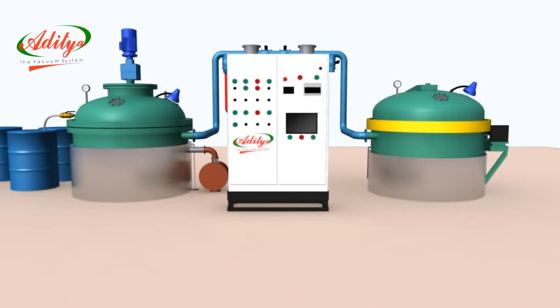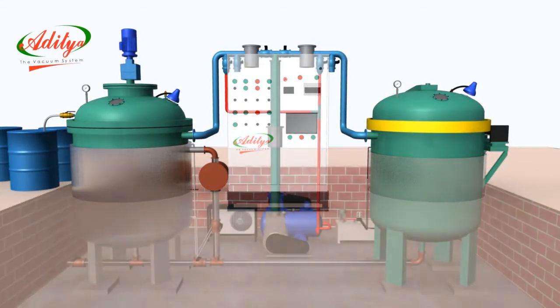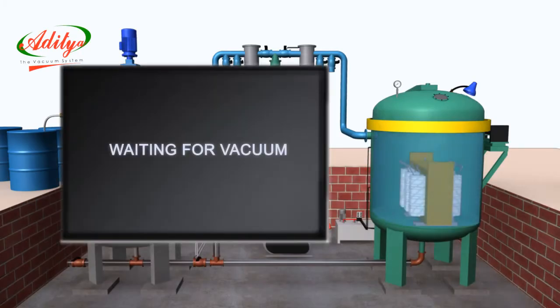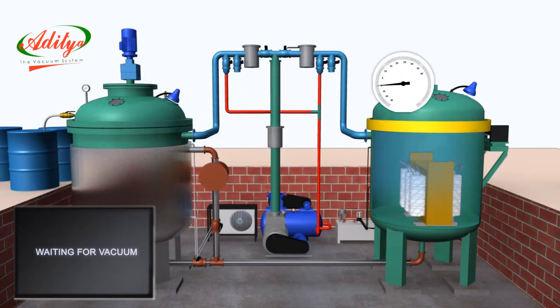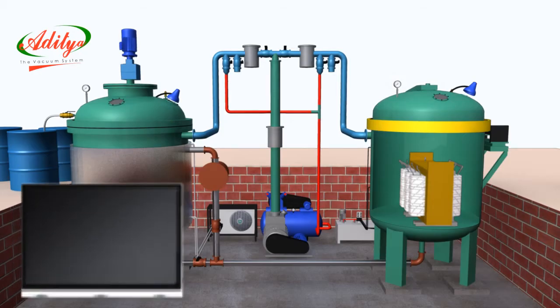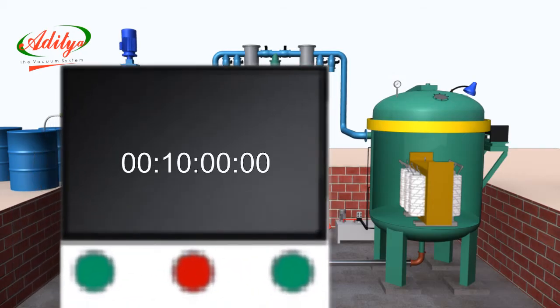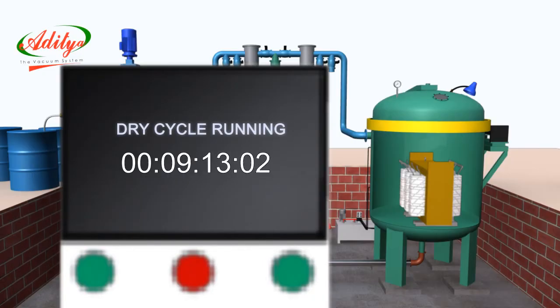First step in dry cycle, vacuum evacuation process is start. Waiting for vacuum. Once the required vacuum is reached, the vacuum system will stop and vacuum evacuation starts. Parallel timer will start, during which the display screen indicates Dry cycle running. In this process, vacuum will drop. Again, vacuum system will start and maintain the vacuum. After completion of dry cycle, immediately next cycle will start.